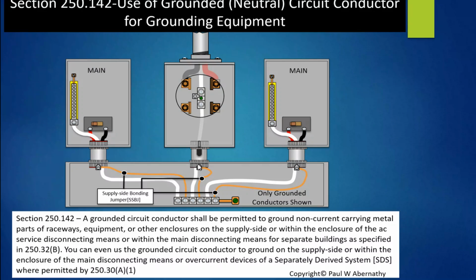Oh, let me go and tell you this. What if I had perfectly punched holes? If I did, then I could put a bonding lock nut on there with a screw that drives into the threading of the nipple, and I could put it here and here and here. If these were perfectly punched out holes, then I would be perfectly fine. I wouldn't need these bonding jumpers, supply side bonding jumpers. That would be considered adequate connection. Okay? But I can't use a standard lock nut except for the mechanical portion. So I could have it on this side, but on the side that's inside the raceway, or the gutter here, I would use a bonding lock nut, or in this case, a bonding bushing with a bonding jumper, because I encountered some concentric or eccentric knockouts.